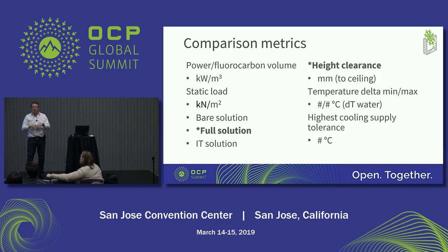So first of all, static load is defined by kilonewtons per square meter. It's used in construction. Sorry, can't help it. It's what construction engineers are used to working with, not kilograms, but kilonewtons. Now, there's a difference between bare solution, full solution, and IT solution, and that's relevant. If you have a bare solution, something that you buy and is delivered to you, if you buy an immersion system, open bath, you get the tank. It doesn't contain liquid yet, it doesn't contain IT yet. But you need to move it to that location inside a data center, and it's still a pretty heavy device. It's not like a bunch of servers or an empty rack that's only maximum 100 kilos. It might be a very big rack that is very heavy, and you need to make sure that the whole route towards that white space can take that load. Very basic little thing that you just need to be aware of.